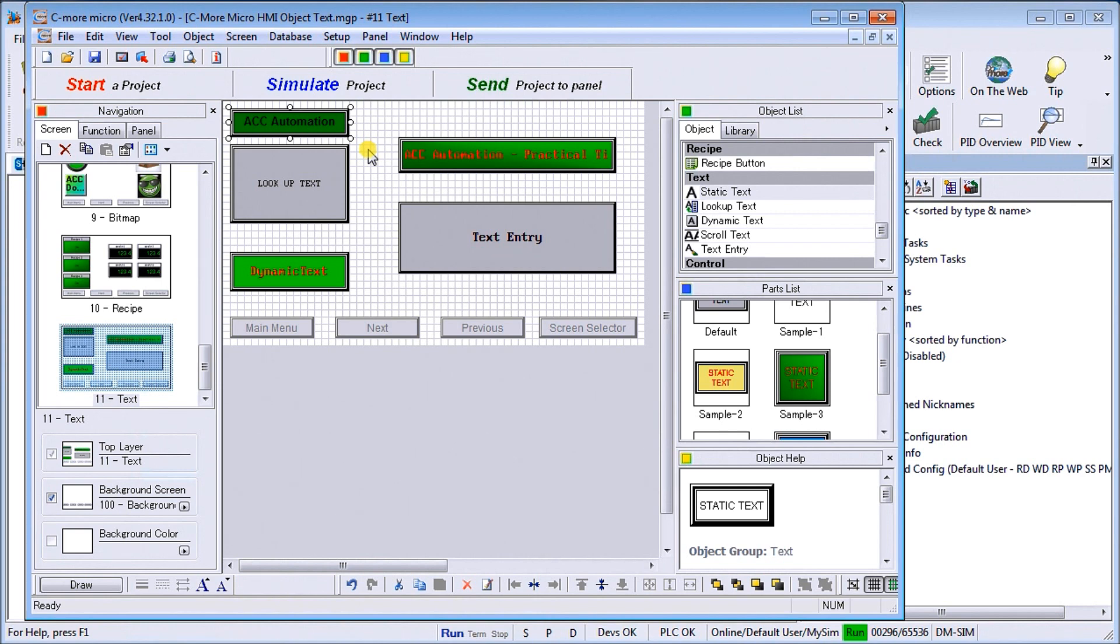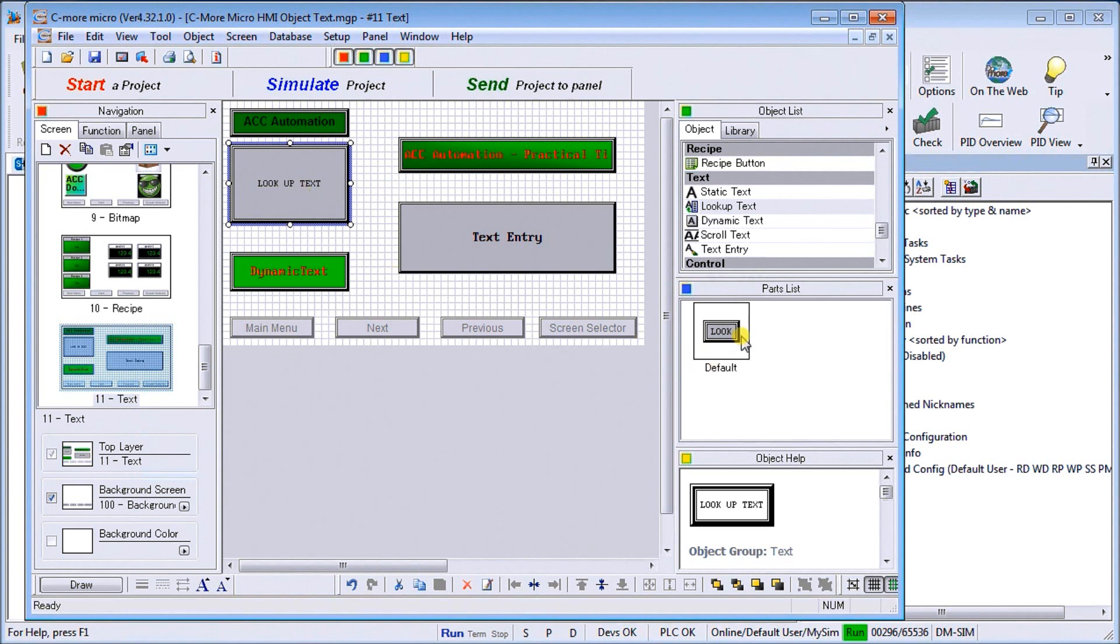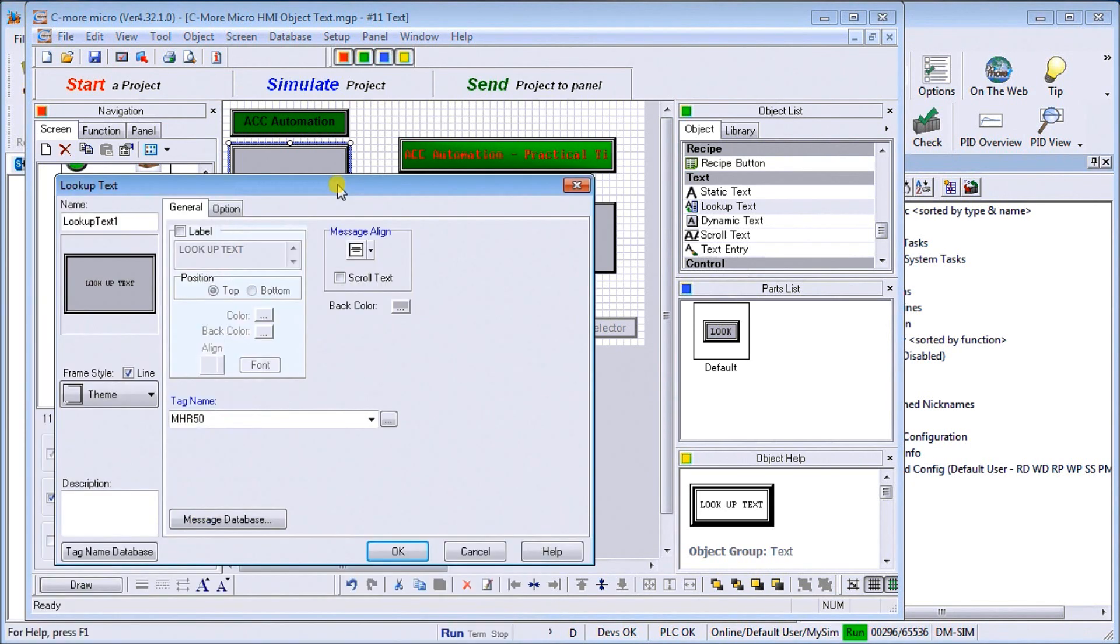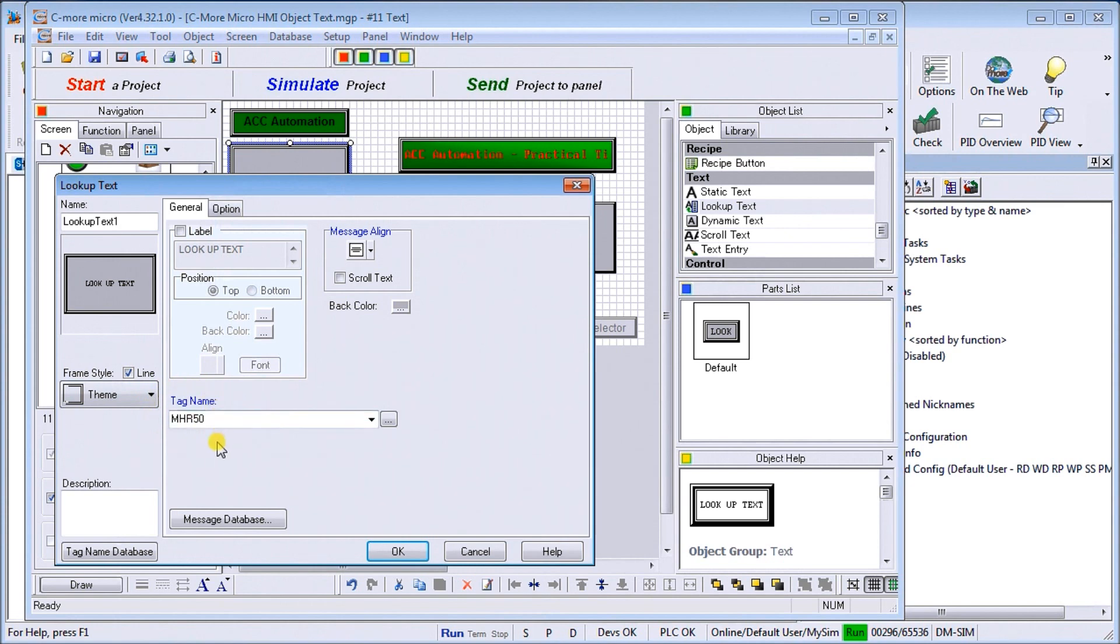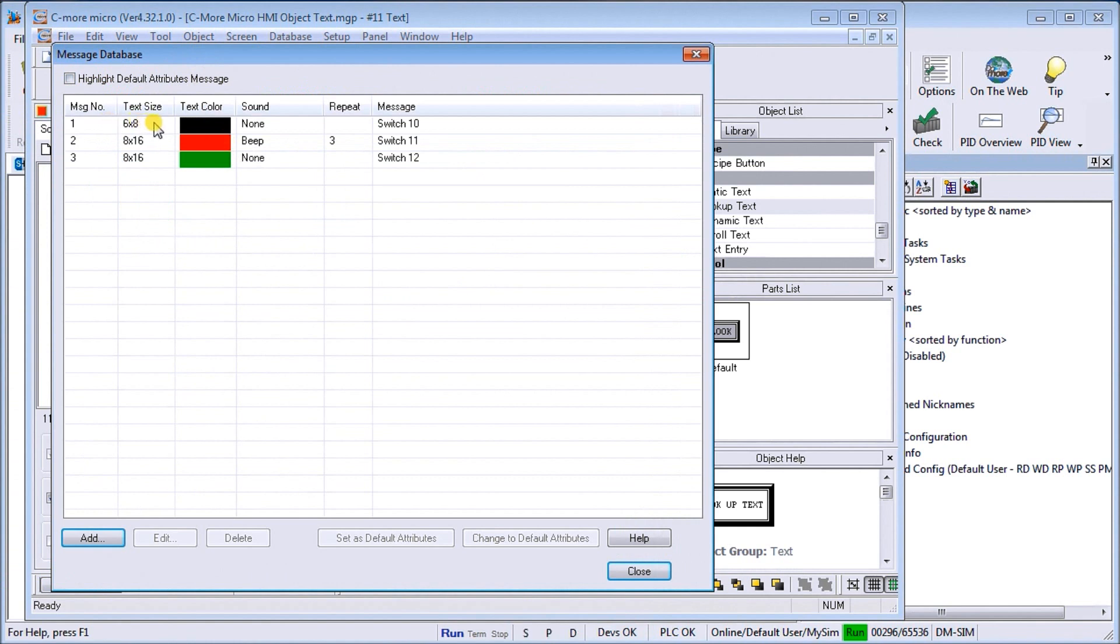Next one, if we look up, we have lookup text. The lookup text, which is this one right here, there is no pre-built parts, so we'll just double click on it. What it will allow us to do is to take a tag name, and within that tag name we specify the tag name itself. In our case here it's MHR 50, and based on MHR 50, it will call up predetermined tags that we have within that word. So as we call up the word and we have a number in that word, it will automatically call up the message that we want. In our case here, we have three different messages that we've programmed in here.